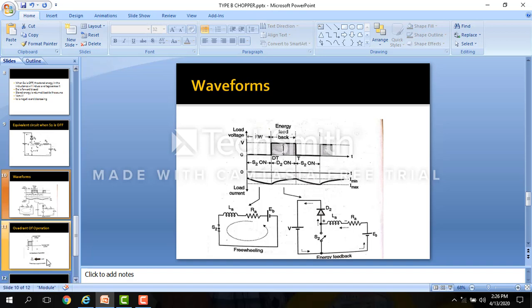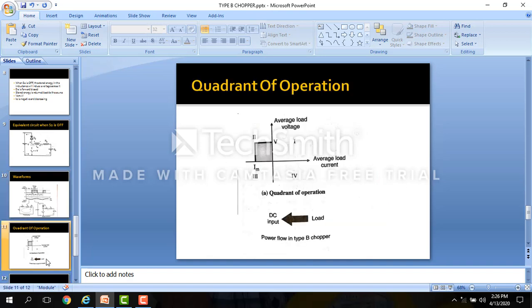This is the regenerative chopper. The DC motor in this case acts for a short duration as a generator, and the kinetic energy stored in the system is returned to the input DC source. Due to electrical loading, the speed of the DC machine decreases, and the higher the current drawn from it, the faster will be the reduction in speed. This is known as regenerative braking of the motor.